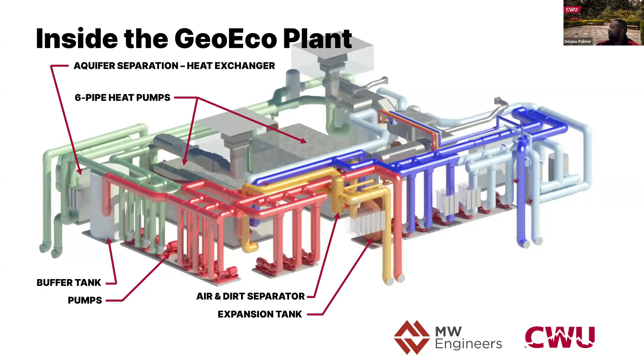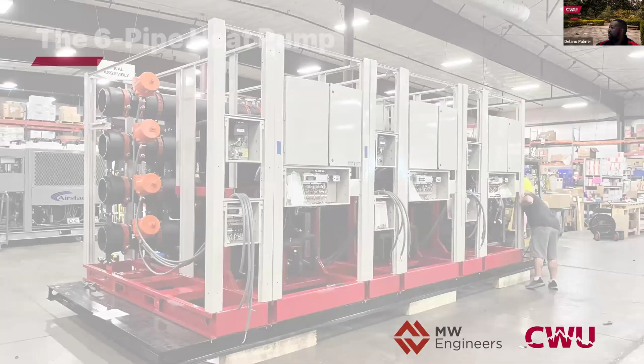Inside the GeoEco plant, we're using a 6-pipe heat pump system. The green piping represents groundwater coming from our well before it goes to the heat exchanger system. Red piping represents our district low temperature hot water supply and return, and the blue pipe represents our chilled water supply and return throughout campus.